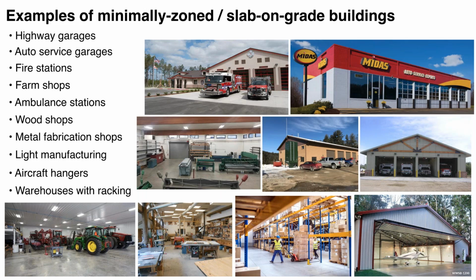And the fact that they have a slab floor and would be good candidates for floor heating, how can we bring in air to water, as well as, I should mention, pretty much everything that I'm going to describe around air to water would also work with a water to water geothermal system. So the same or very similar system configurations. The reason I picked air to water in this is if you have existing buildings, in many cases you don't have the opportunity to install a geothermal system without extensive disruption of the facility or the grounds around the facility. So this is that niche of buildings that we're kind of identifying.